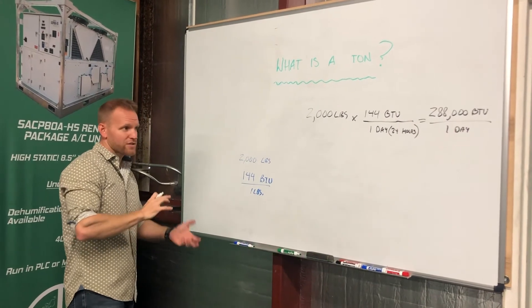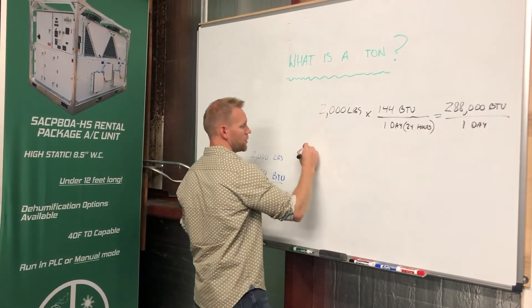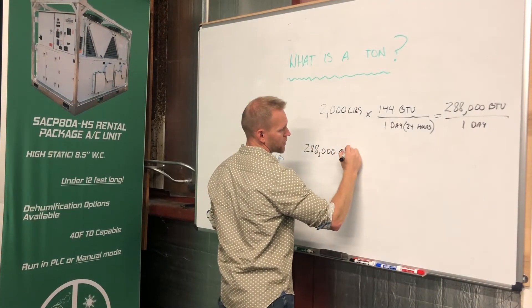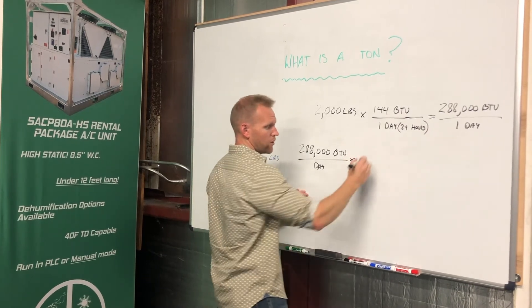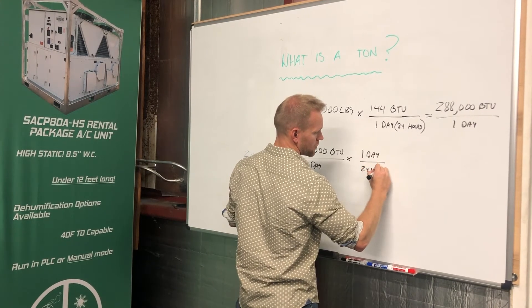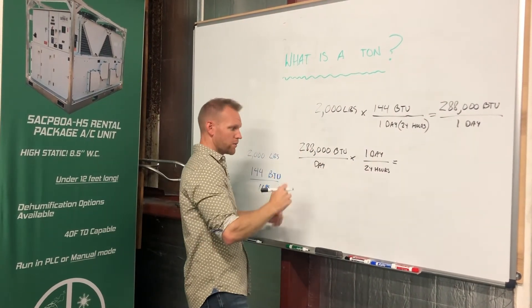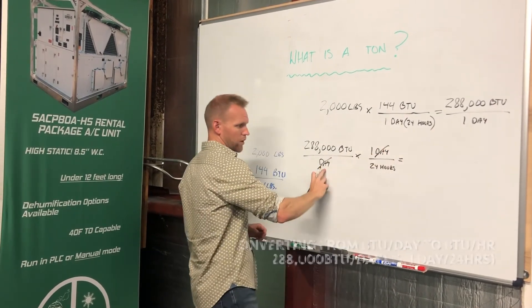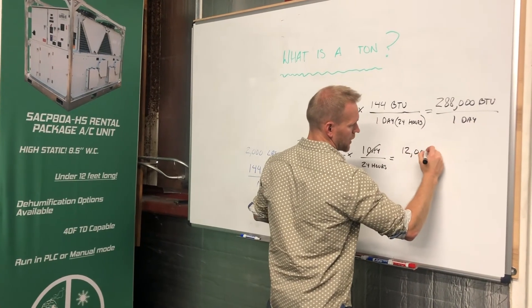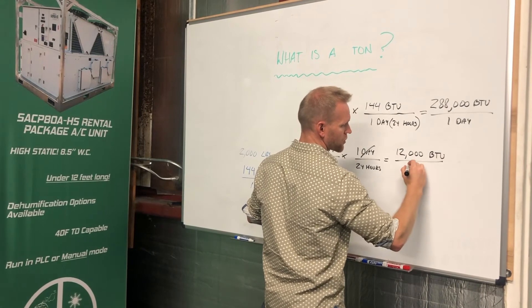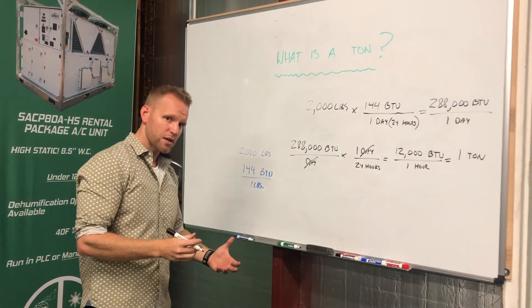So how does that equate to the capacity required on a per-hour basis, which is normally how we represent tonnage in air conditioning systems? That's also pretty straightforward. We know we have 288,000 British thermal units per day — that's one ton — and we know there are 24 hours in one day. So we do a standard conversion: divide 288,000 by 24 hours, and we get 12,000 British thermal units per hour is equal to one ton. That's where the standard came from and how it was developed.